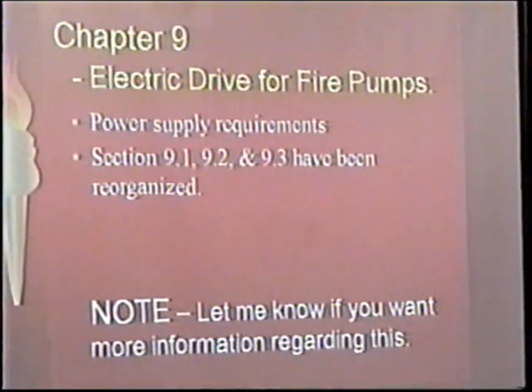The code now says, you've all probably seen the MI cable, the electrical cable that looks like soft copper water pipe. That mineral insulation cable, a lot of it was installed, especially for the bigger pumps. It's one unit per phase. So you had 3 of them coming in the top of the controller. Well, they were never supposed to land those on the controller. They're always intended to be landed at a junction box and then converted to standard wire and brought down through a watertight connection. Again, I have no power to mandate that. Now it's in my code. I can say, hey, that was the manufacturer's wire installation instructions that weren't being followed. So these are the kinds of issues that you'll find out there that the code has tried to help clean up for us.